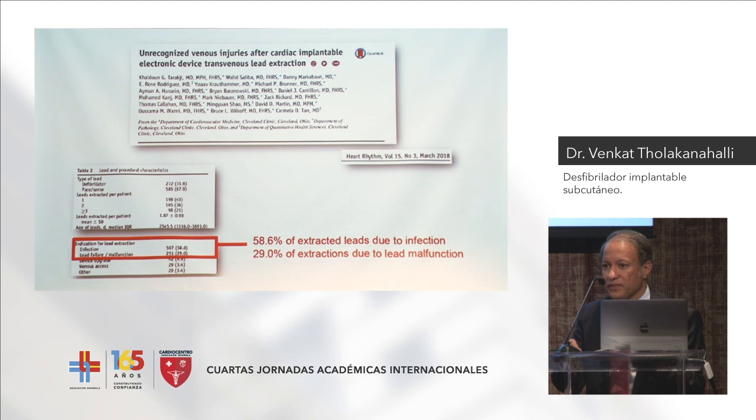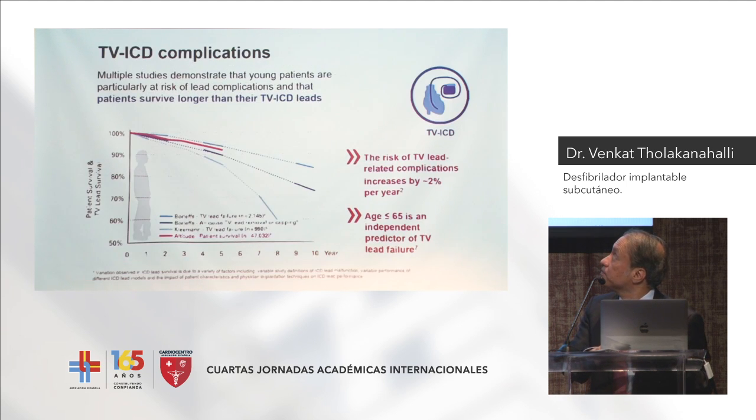Transvenous leads have been debated, and they tried to come up with a lot of insulation materials, combining silicone, polyurethane, multiple things. Despite doing all these things, the stress and strain from the constant activity of the heart's contractility, and also the crush fracture that we see in the clavicular area, is a chronic problem, a huge problem.